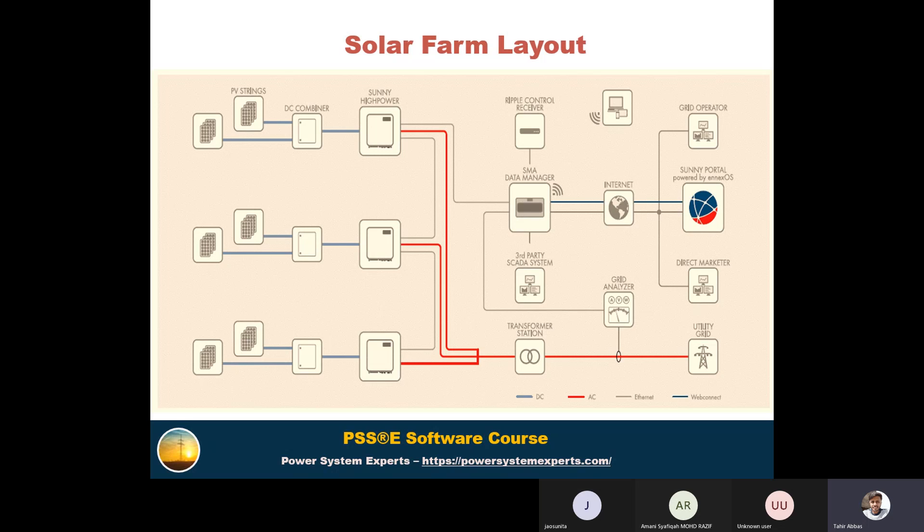In the PV solar farm, a number of PV strings are connected in series and converted to AC through an inverter. After the transformer the plant is connected to the grid, and at the point of interconnection (POI) a grid analyzer is available. A plant controller is also a key function in both solar and wind at the POI — it measures information and applies control to the model. The important thing is that dynamic modeling of wind and solar involves detailed control systems.